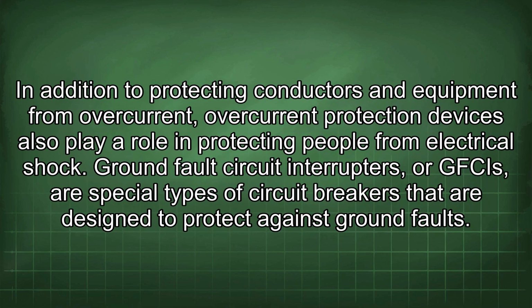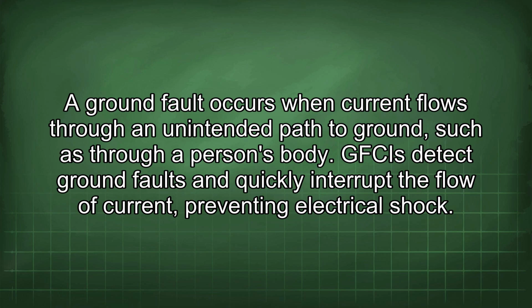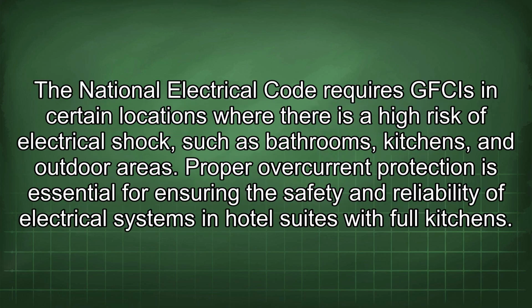In addition to protecting conductors and equipment from overcurrent, protection devices also play a role in protecting people from electrical shock. Ground fault circuit interrupters, or GFCIs, are special types of circuit breakers that are designed to protect against ground faults. A ground fault occurs when current flows through an unintended path to ground, such as through a person's body. GFCIs detect ground faults and quickly interrupt the flow of current, preventing electrical shock. The National Electrical Code requires GFCIs in certain locations where there is a high risk of electrical shock, such as bathrooms, kitchens, and outdoor areas.